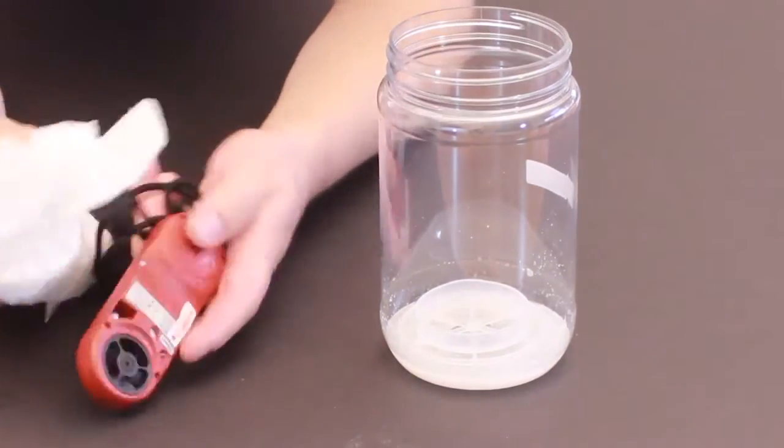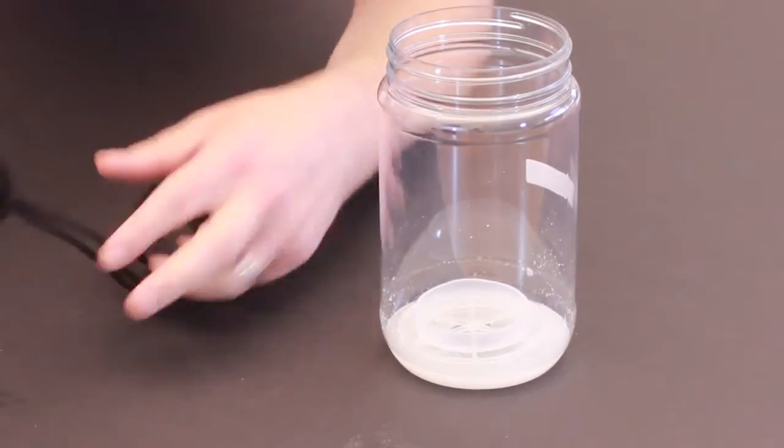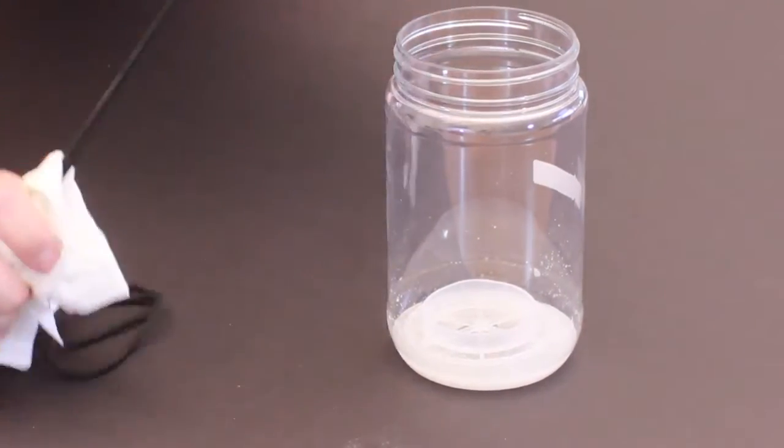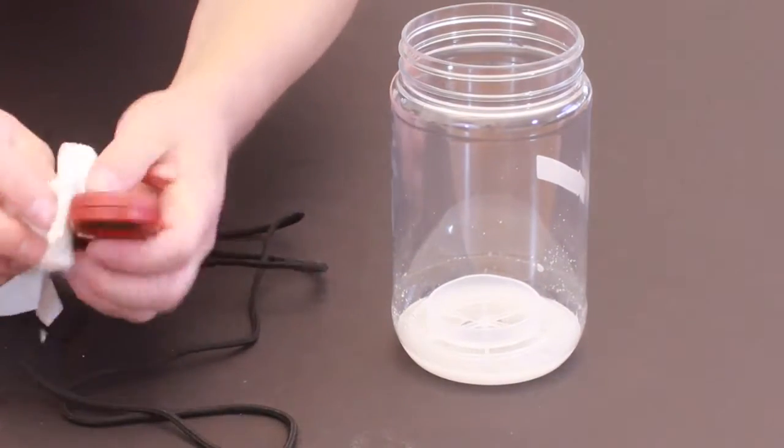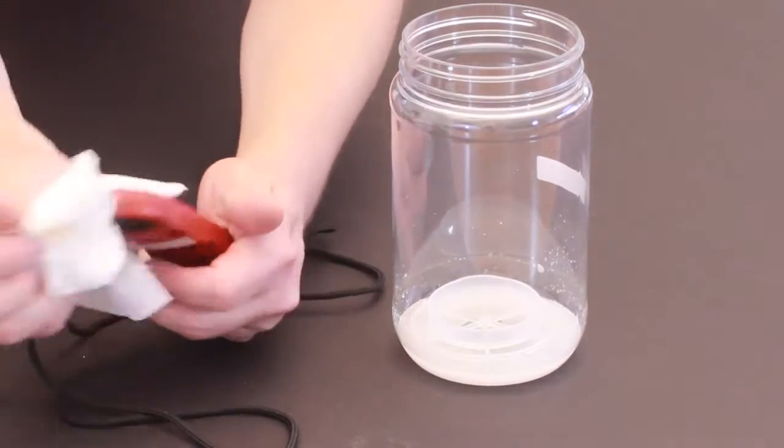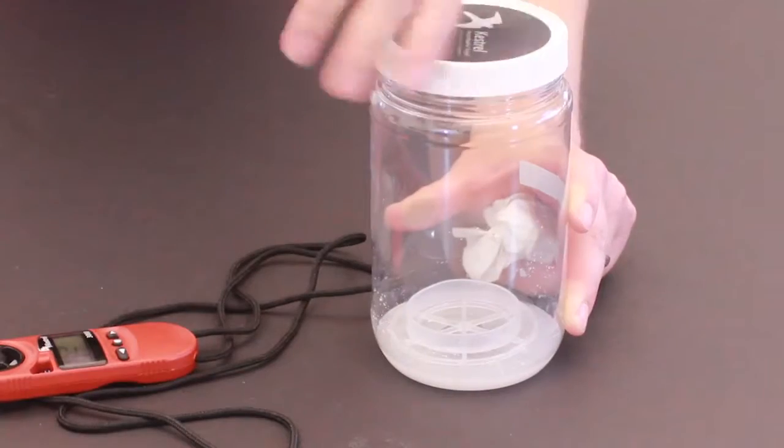It's very important that we wipe down any residual salt or liquid that would be on the Kestrel. Hopefully the spacer kept it from getting wet, but just to be sure, just take a paper towel and make sure that there's no excess salts on here. Now we can close the magnesium chloride chamber.